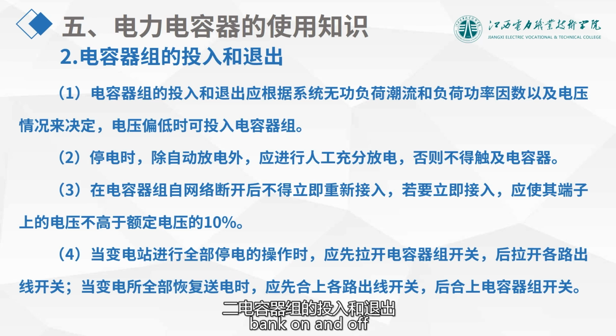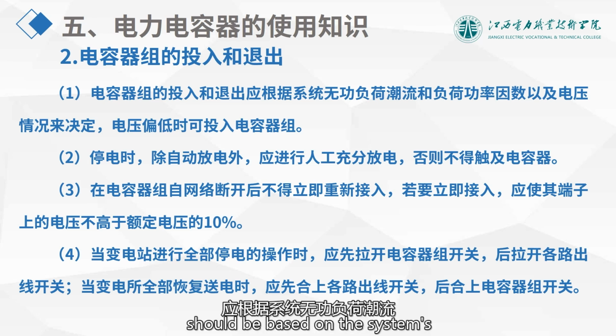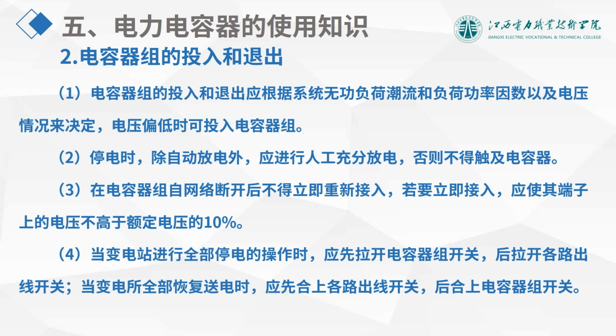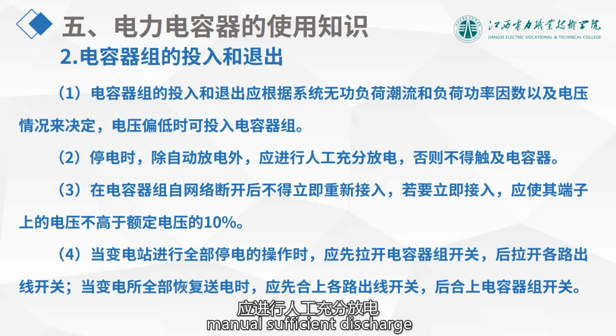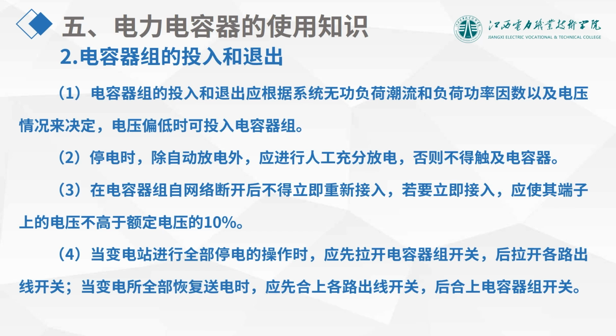Switching the capacitor bank on and off. The switching of the capacitor bank should be based on the system's reactive power load flow, load power factor, and voltage conditions. When the voltage is low, the capacitor bank can be switched on. When powering off, in addition to automatic discharge, manual sufficient discharge should be performed. Otherwise, do not touch the capacitors.